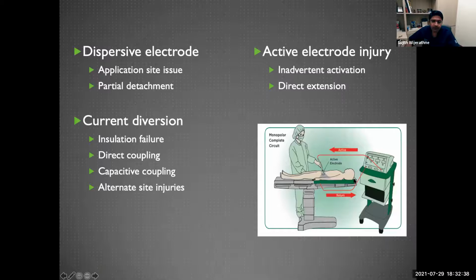In the usual monopolar electrosurgery we use, there are a few sites where injury can happen. One is the dispersive electrode. With the dispersive electrode, there can be application site issues, which we will talk about in a short while. There can be partial detachment. The current electrosurgical units are actually capable of detecting most of these dispersive electrode issues. So it doesn't allow you to use the active electrode if there's an issue with the dispersive electrode. Most of the new ESUs are equipped with this function.